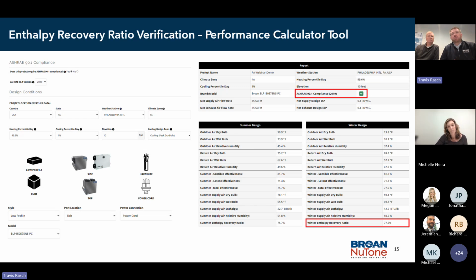That report includes all your project information, plus a green checkbox confirming you're compliant with 90.1, based on your enthalpy recovery ratio. Because of the climate zone we're using here, we need to be at or above 60%. In this example, we're at 77% or above, so it's easy to check that box—and we're only concerned with the heating design condition, the winter condition.